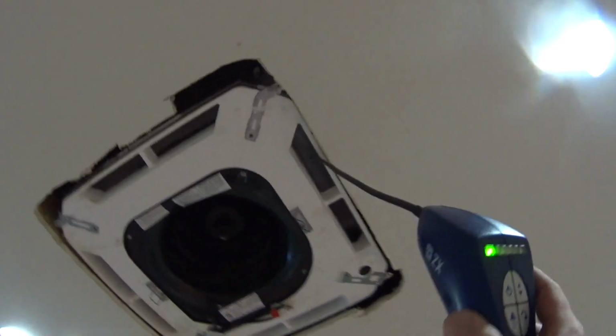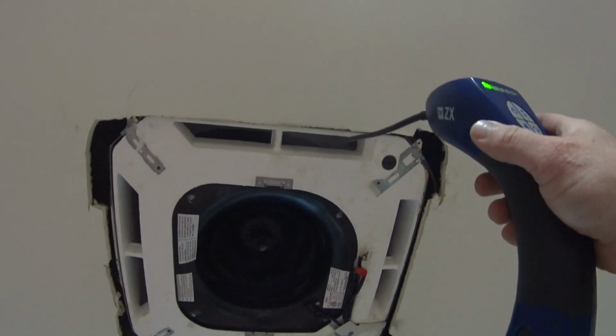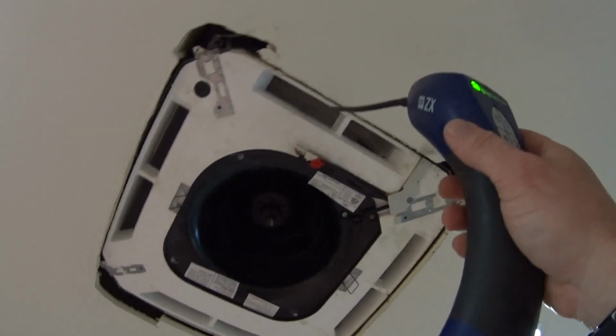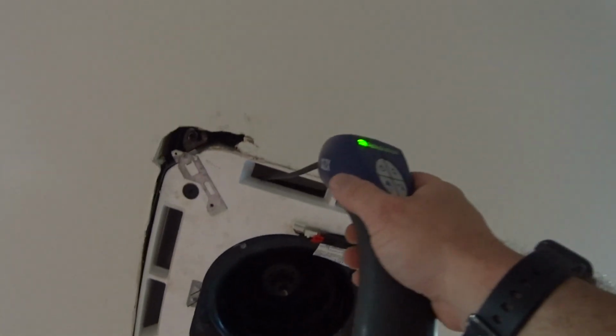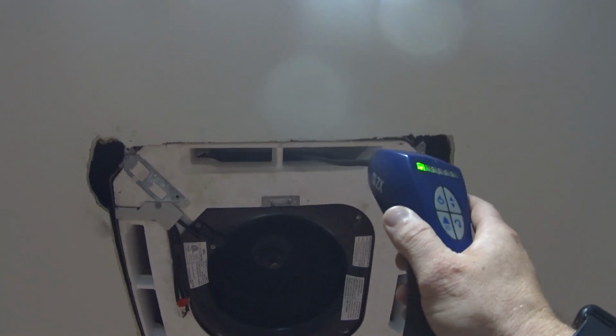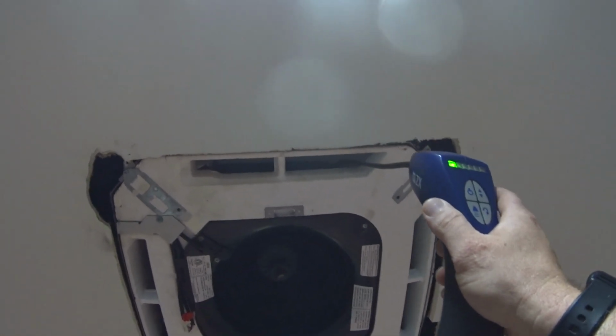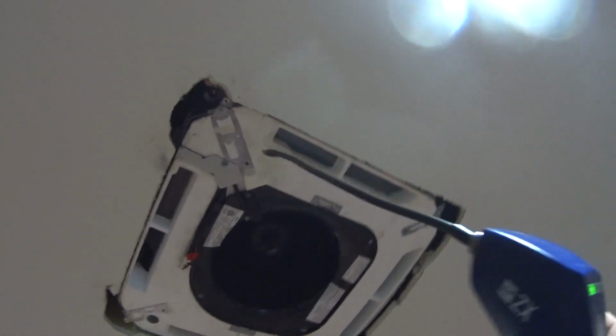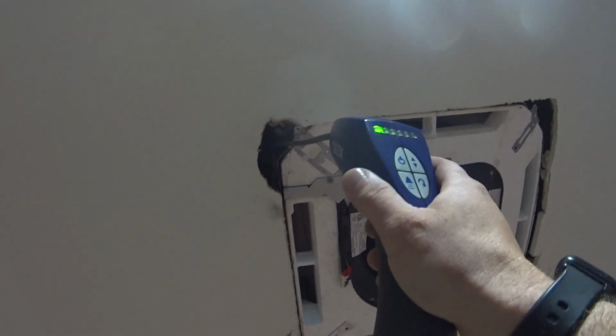The initial check going up through the louvers of the ceiling cassette was inconclusive. Didn't show anything that was indicative of any leakage. So I've pulled the frame down to see if I can maybe get something without the louvers, since it does limit access a little bit. I'll proceed to pull down the blower here once we give it a cursory sniff. I may be moving a little faster than maybe I should, but this leak detector has proven to be quite sensitive and has shown leaks fairly quickly.